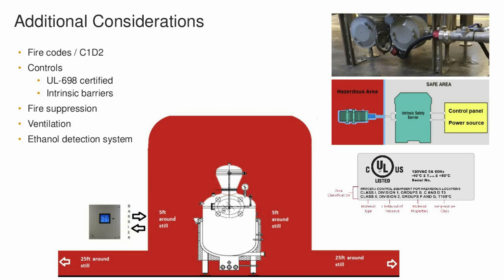So if there's a short in the control panel, we have what's called an intrinsic safety barrier. That safety barrier will take care of any surge of electricity, so there's no chance of any spark or anything happening at the sensor. So those intrinsic barriers need to be built into the control panel, and that's very key as you start considering what your still design is going to be. And if you have somebody do the controls, make sure that they're UL 698. UL 508, which is typically in your brewing panels, is not going to be enough. The UL 698 is the UL version, and it could be CUL for Canada, UL for the US, and also actually all South America. I know we have someone from Mexico, Costa Rica, so the UL typically is fine and accepted in that area, but you have to have that UL 698 in order to properly install the intrinsic safety barriers.